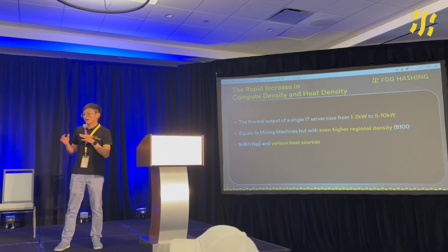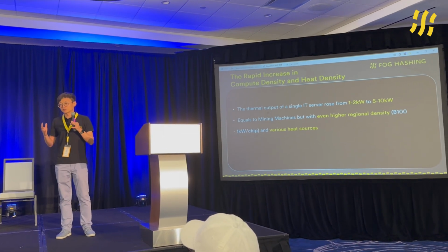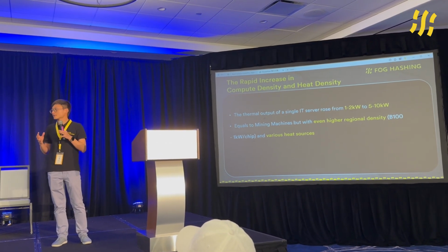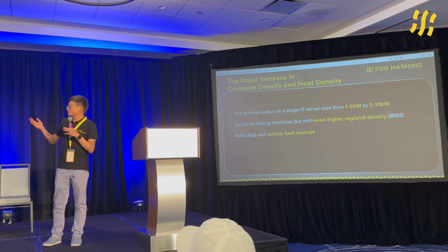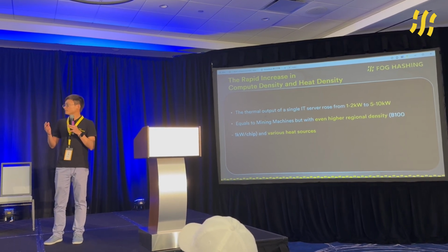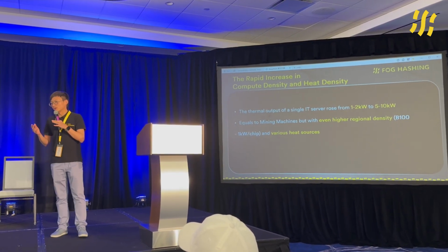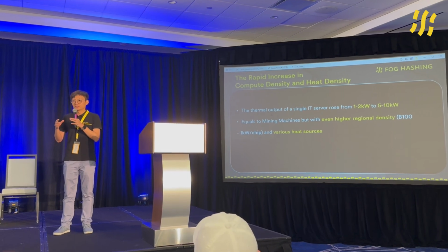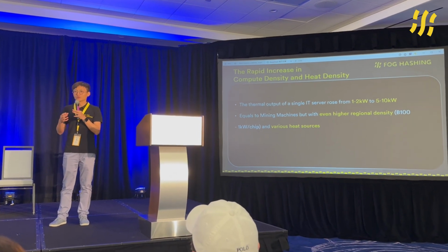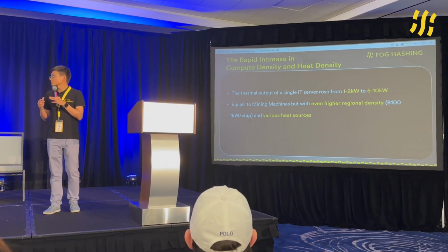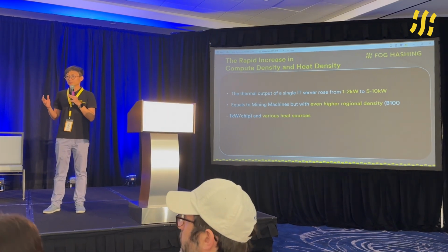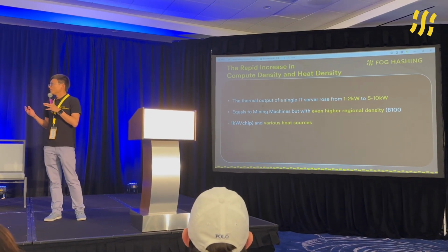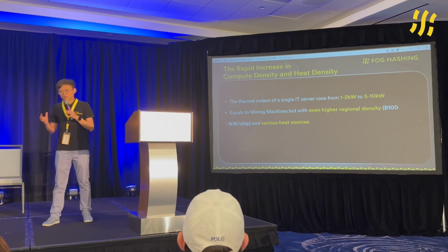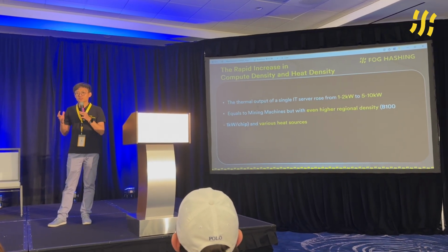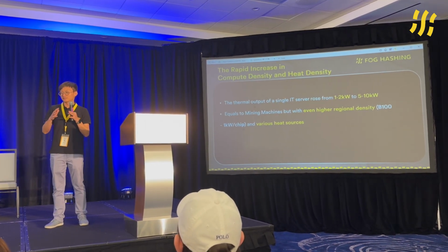But now, as the thermal density is almost the same, the latest B100 from NVIDIA comes up to 1 kilowatt per chip—one single chip, 1 kilowatt. It's ridiculously high. So for the next generation, liquid cooling will be the default cooling method rather than air cooling.